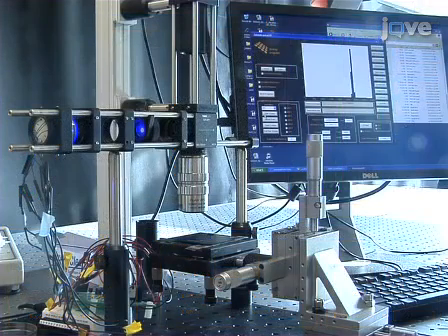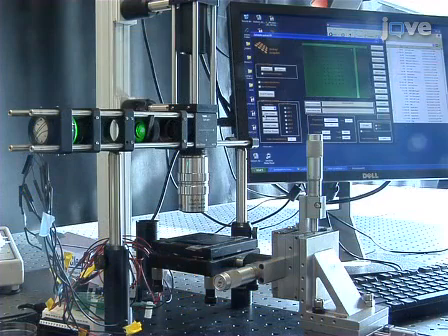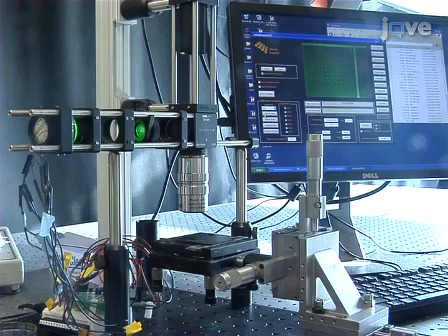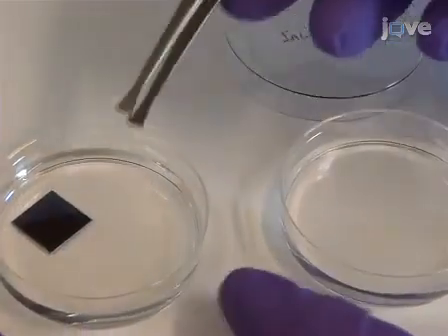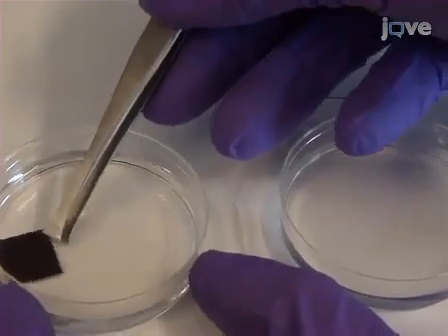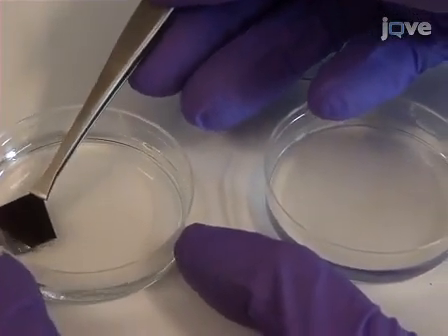Initialize the software to scan the array, which illuminates the surface at different wavelengths many times and averages the collected images. The initial optical height at each spot is determined, allowing for proper analysis of changes in mass on the surface after the incubation. Following the initial scan, submerge the chip in the prepared incubation solution for 1 hour on a shaker plate.